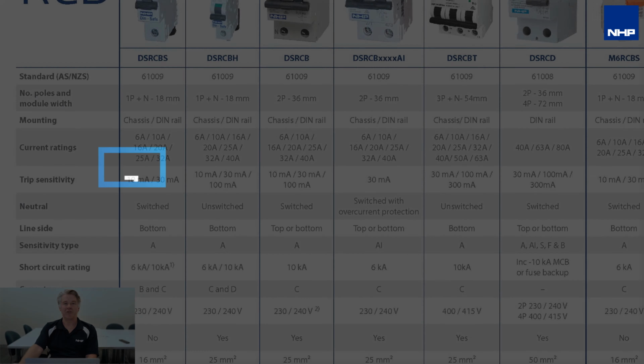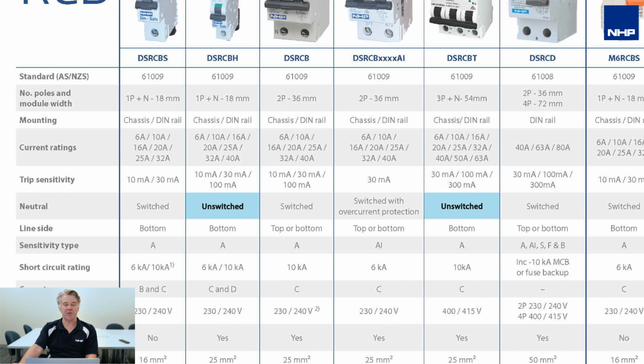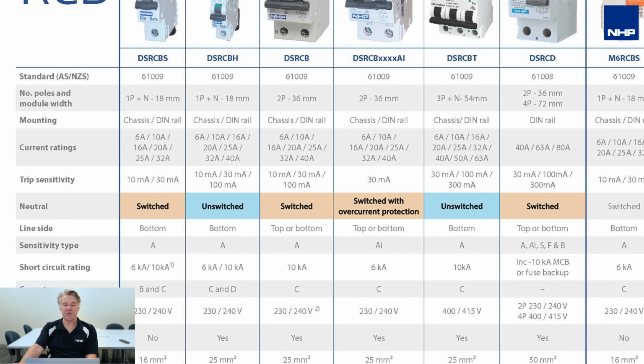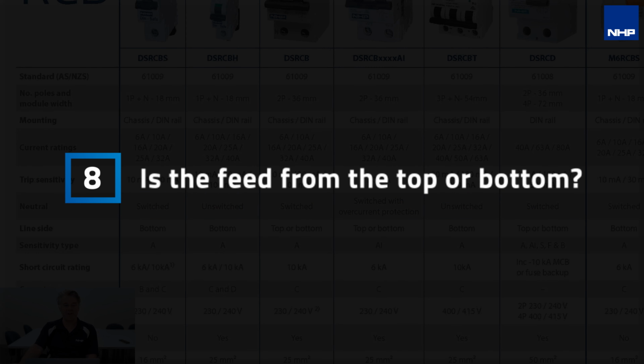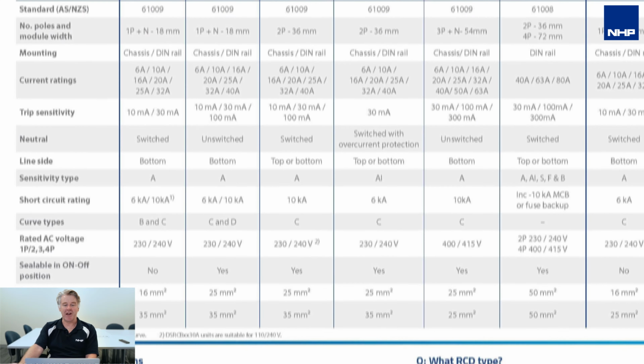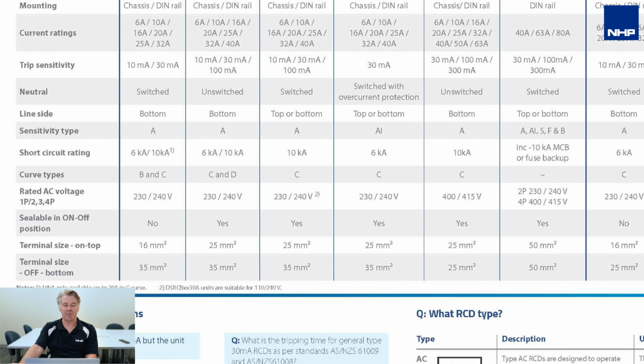The application, does it require a switch neutral or not a switch neutral? Generally, unswitched neutral is all that is needed, but you may have some higher risk applications, such as in a service station or a site-specific requirement where you require a switch neutral. So then you need to ensure you meet that needs according to this line here. Is the feed coming from the top or the bottom? Generally speaking, the feed will come from the bottom, but you may have applications where the line side is on the top. So it's important to make note of that also.